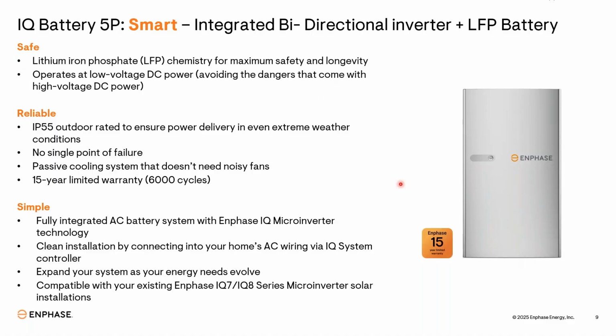On your roof, if you see microinverters, they come with this feature also: no single point of failure. Every single module has a single microinverter. So if a microinverter fails, the other modules will keep working. Same inside this battery. This battery comes with 6 bidirectional microinverters. Each microinverter gives you an output of 640 VA. So in total, all 6 microinverters make an output of 3.84 kVA. If one microinverter fails, the remaining 5 give you output. So 640 multiplied by 5, that output you are going to get from the batteries. There is no chance all microinverters will shut down at a single time.